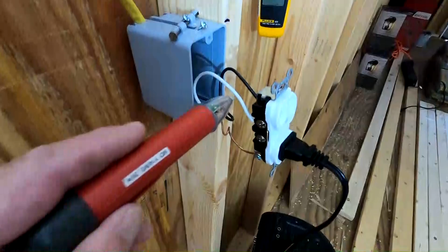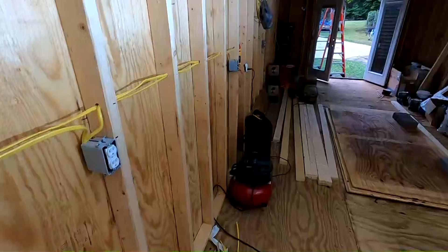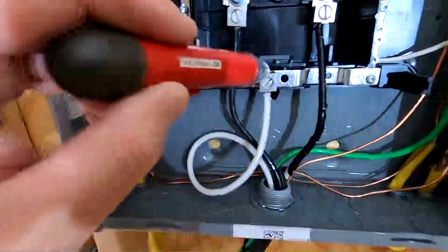We've got a bar back here called the neutral bus bar, and that's where we hook all our whites and neutrals that come down and tie in. This is the neutral wire, which now goes back to the power company. When voltage comes in, goes through the breaker, it wants to go out and do work, turning on lights, air compressors, battery chargers, radios, hair dryers, and so on. It comes back in and has to get back onto this bar, or nothing's going to work.